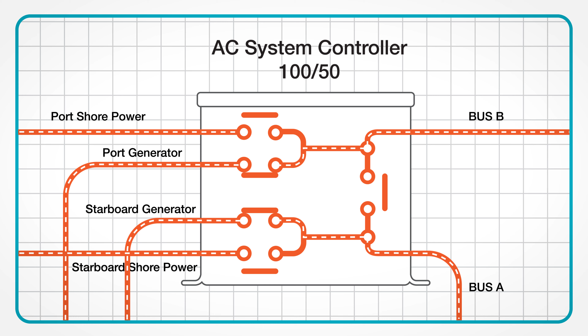So we'll start up our starboard generator, and we'll see that it disconnects the starboard shore and connects the starboard generator instead to supply Bus A. Similarly, if we started the port generator, that would take over from the port shore power. So if you were leaving your mooring, for instance, you might start both generators, and the boat would then run off the generators. You could disconnect the shore cords and avoid any interruption to supplies on board the vessel.